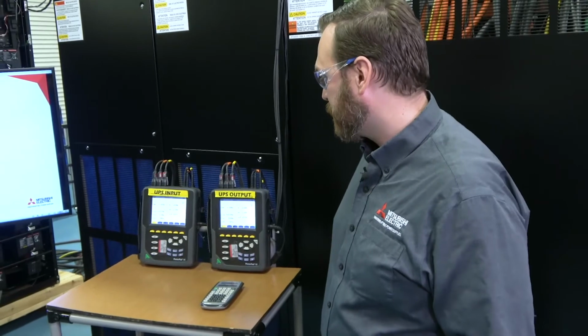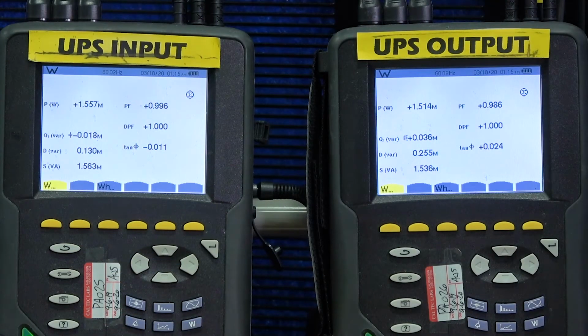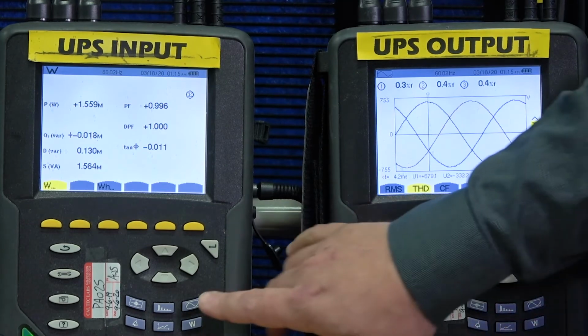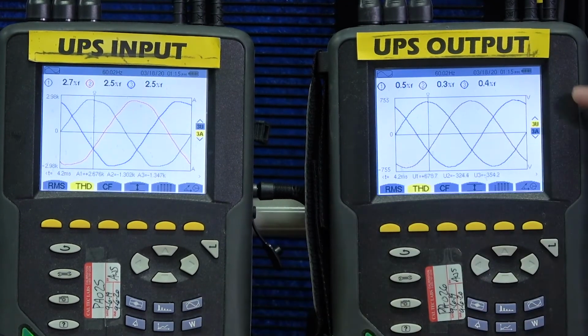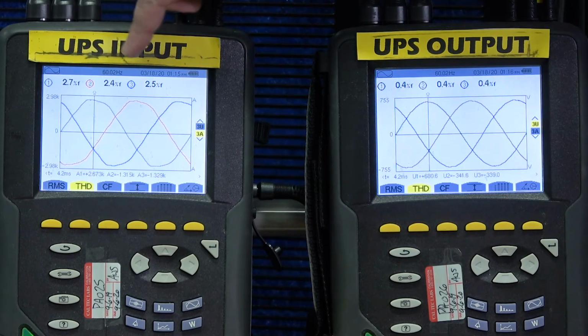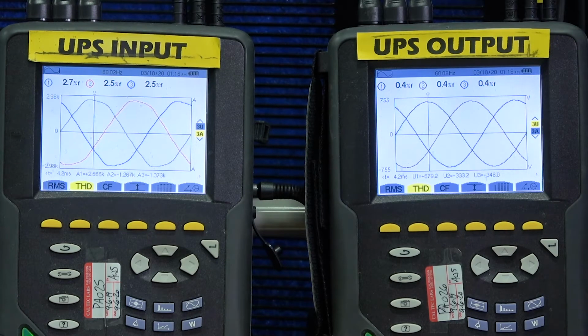From here, we're going to increase our load up to 75% load. So 1.5 megawatts on a 2 megawatt UPS system. Again, we'll take a look at our input and output harmonic content. Our output is still declining down to about 0.3% output total THD on the voltage, as well as 2.7, 2.4, and 2.5% input total current harmonic distortion. So as I said, it would continue to decrease as we approached 100% load to well within spec, and we're currently at 2.5%.